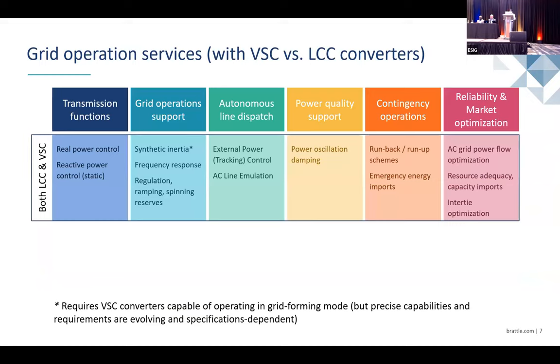And these converters can also do grid support, especially frequency response. For example, if the frequency is changing beyond the acceptable range, HVDC will automatically control the power output to the grid to bring the frequency back to the acceptable level. Similarly, if you are connecting two grids with HVDC and there is an event in one of the grids, you can get support from the remote grid, like inertial support or spinning reserve support. There is no need to have it for each side; you can get it from the other side.